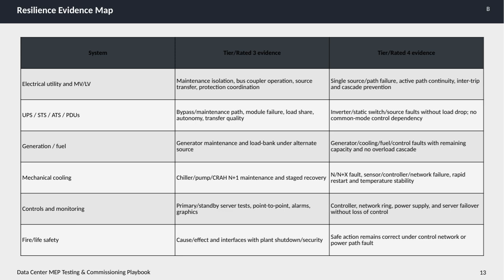Controls and monitoring at Tier 3 involve primary and standby server tests, point-to-point communication, alarms, and graphical interfaces. Tier 4 adds robustness with controller failover, network ring resilience, power supply backup, and server failover, all without loss of control. Finally, fire and life safety systems at Tier 3 validate cause and effect responses and integration with plant shutdown and security. Tier 4 ensures safe actions remain correct even under faults in control networks or power paths. This map essentially highlights the progressive steps in testing and commissioning that ensure higher tiers of data center resilience and operational reliability.